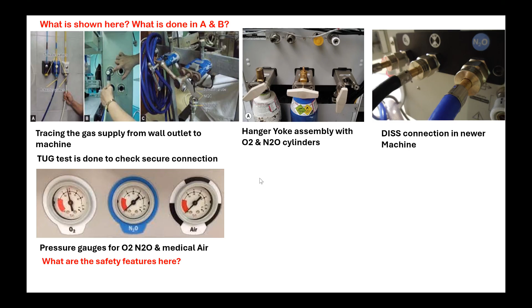Now here you can see oxygen is in a safe limit. But as the needle comes down when the oxygen is being used from the cylinder, when it comes to the red zone, you will have to be alert. Earlier it used to silently go to zero. But nowadays, as it touches the red line, you will have an alarm or be cautioned that the pressure is dropping. We have to ask somebody to check and replace it. Everything is color coded and the name of the gas is also written there. These are all the safety features: color coding, name of the gas, and the pressure drop zone.